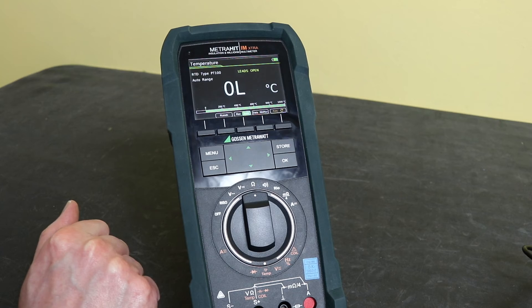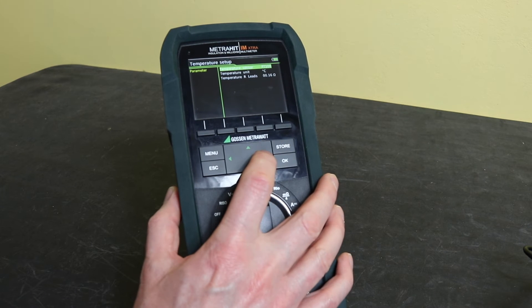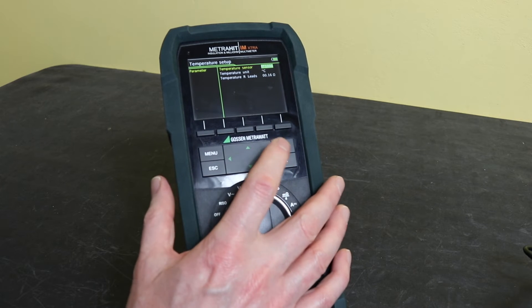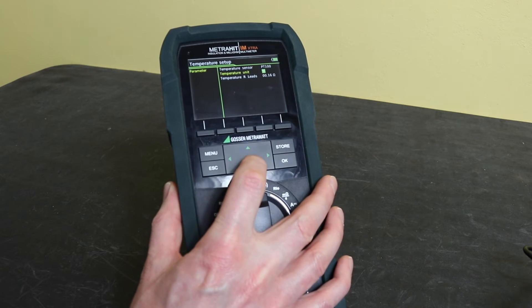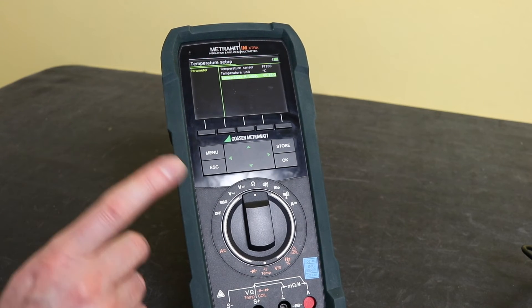You can switch between degrees Celsius and Fahrenheit via the menu. In the menu settings for temperature measurement you can change the temperature sensor type between PT100 and PT1000, adjust units between Fahrenheit and Celsius, and set a nominal lead resistance to null out your leads when measuring with an RTD rather than a thermocouple.